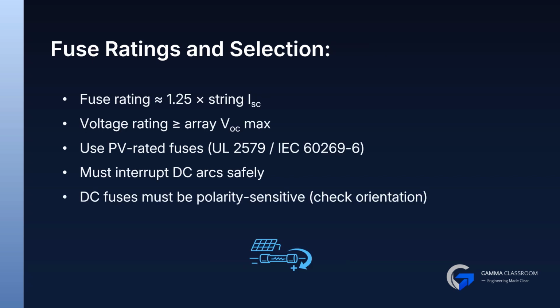Fuses must handle the maximum current and voltage of your array. Underrated fuses can fail prematurely, while overrated fuses may not protect at all. PV rated fuses are designed specifically for DC arc interruption, which is critical in solar systems.